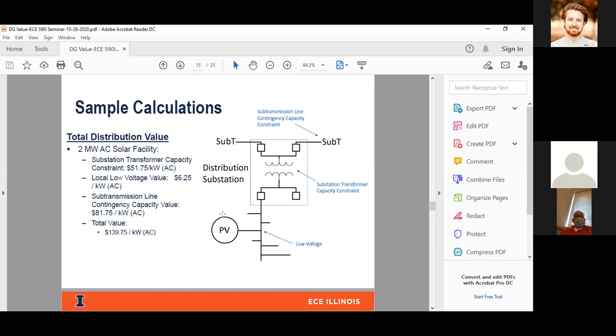And the idea here is be able to calculate these values for each or for different types of DG and produce those values out on, say, a heat map or on some kind of a system-wide view where customers can come in, log in and say, oh, okay, I see the value there, for example, at 139. The customer does their own financial analysis and decide, yeah, that helps me and I'm going to be able to break even or make money on that investment and go ahead and install there. Versus on a different circuit where there's no value, so it helps you really as a developer and as somebody that's trying to add more DG to the system to plan ahead accordingly.